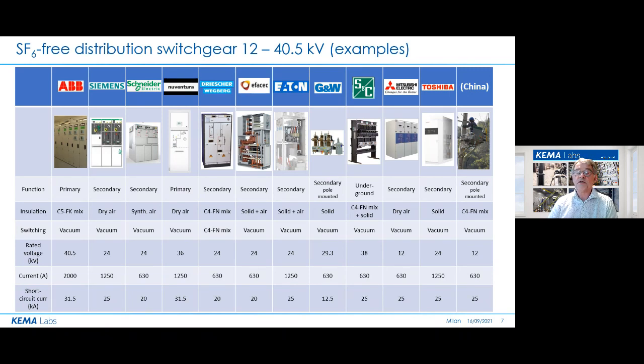In distribution, C5FK is used here along with C4FN. The reason is the lower filling pressure compared to HV. This enables relatively high F-gas content while still keeping an acceptably low operation temperature. As we will see soon, low operation temperature, high F-gas content, and high pressure cannot be combined. In some products, arc interruption is taken care of by one of the new F-gases. These are the load break switching devices.